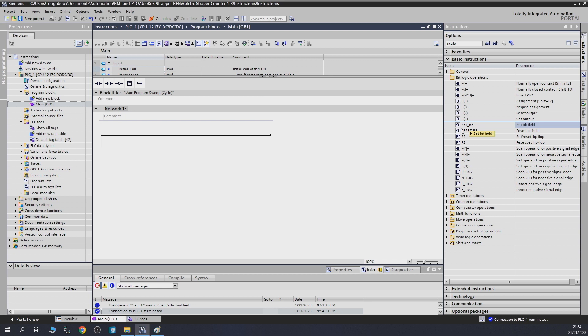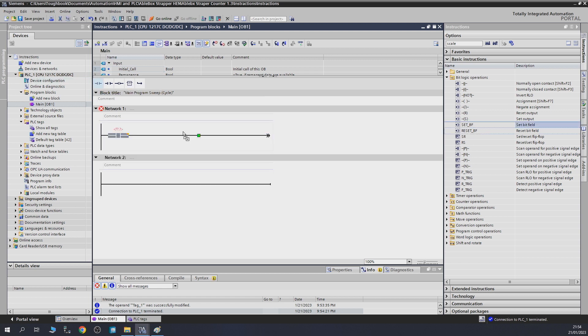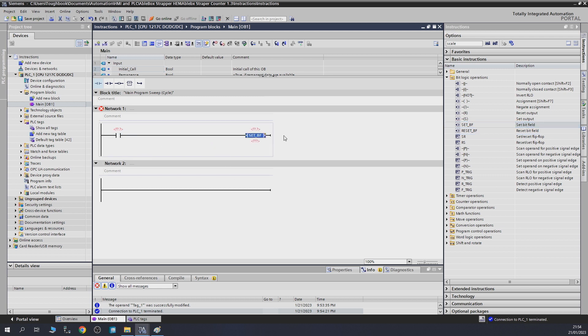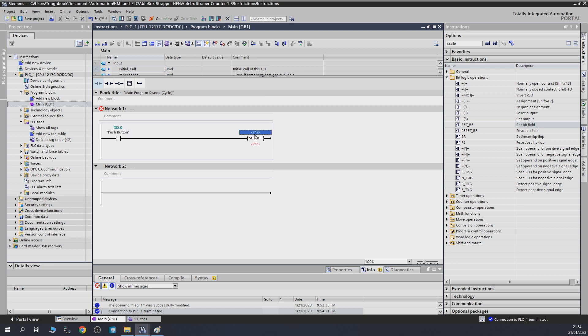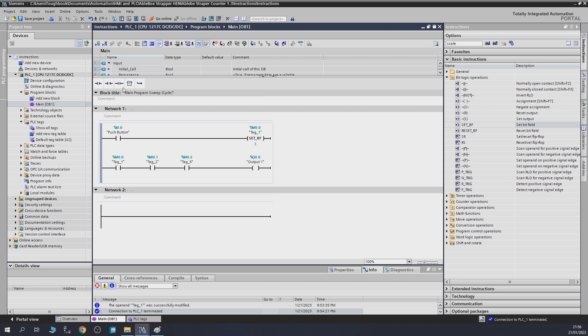Next let's look at SET bit field and RESET bit field. Let's put a contact and drag in a SET bit field. Set bit field and reset bit field are quite useful if you want to set many bits in one go. Let's put our push button in there. At the top you enter your address, and the number on the bottom is how many bits after that address you want to turn on. Let's say M0.0 and we'll set 3 bits — so it will turn on M0.0, M0.1, and M0.2.